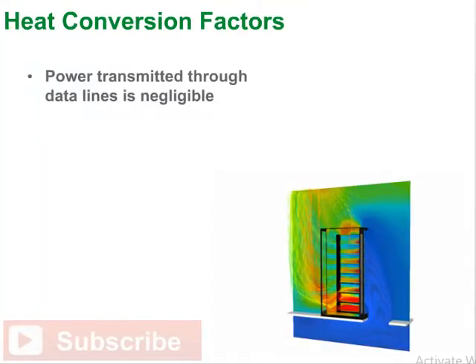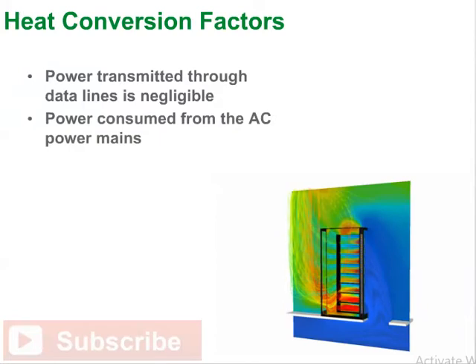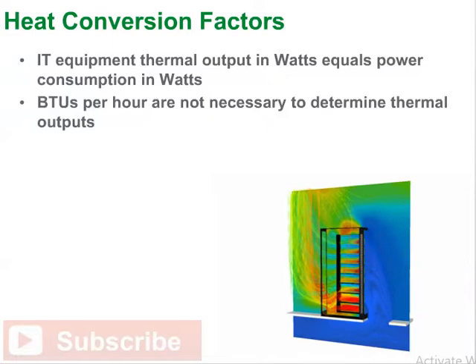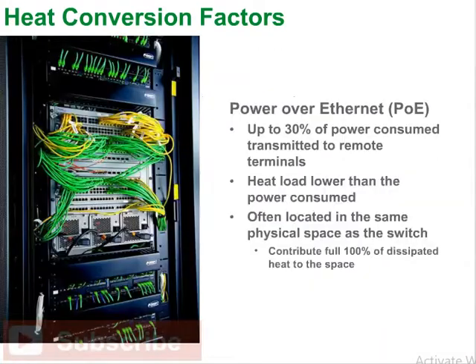The power transmitted by computing or IT equipment through data lines is negligible. Therefore, the power consumed from the AC power mains is essentially all converted to heat. This means the thermal heat output of IT equipment in watts simply equals its power consumption in watts. BTU per hour, as sometimes provided in data sheets, is not necessary — the thermal output is simply the same as the measured power input. The one exception is Power over Ethernet, or PoE, switches, where up to 30% of the power consumed may be transmitted to remote terminals, so their heat load may be lower than the electrical power they consume.